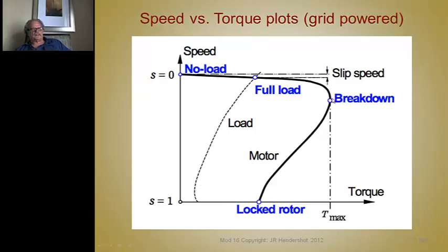And so the torque builds up, and of course the torque requirement of the fan builds up, but the fan won't go any faster than the speed at which the intersection of the two loads cross each other. And the induction motor won't go any faster either. It won't go any faster than this RPM either, because the load is holding it there. And that difference between that speed and the no load speed, the synchronous speed, is the slip speed. And this is the breakdown torque.